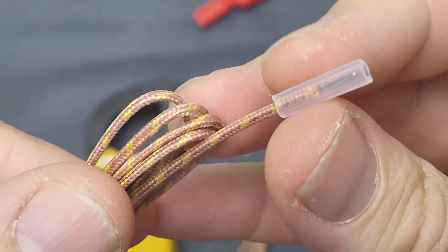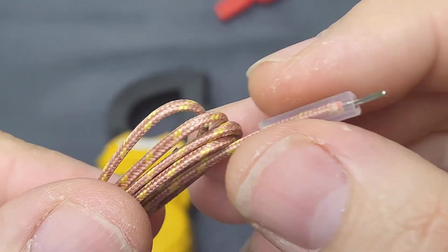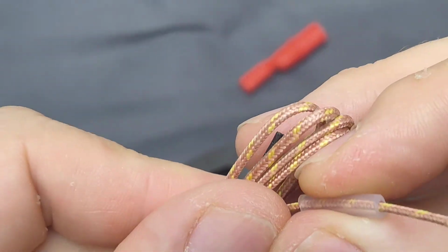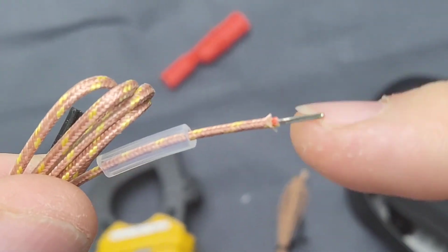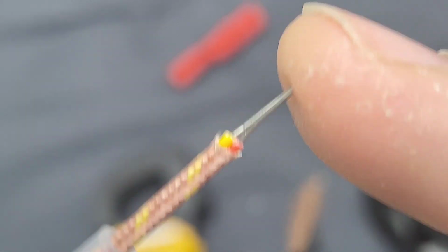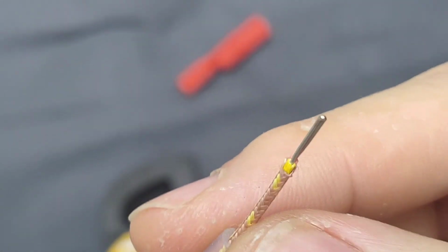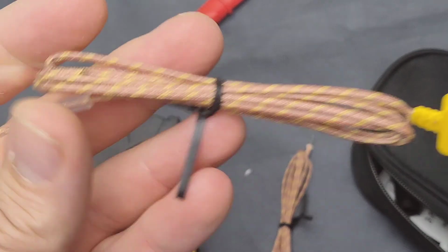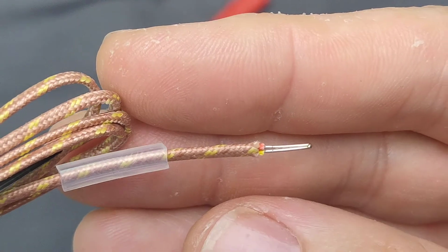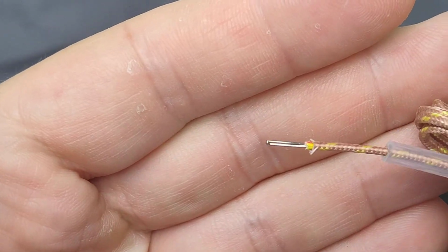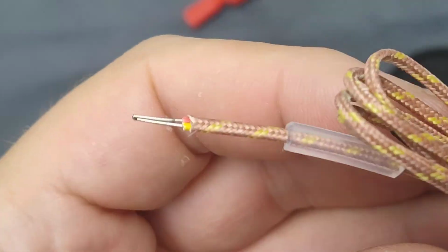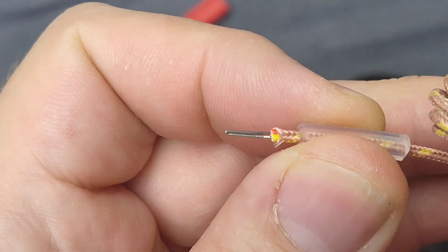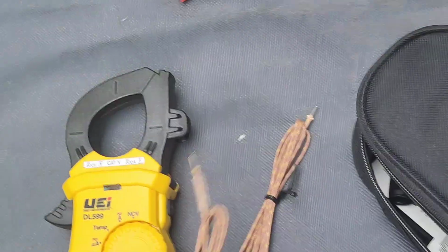Usually position that and put a little tape on it. I prefer to use a little bit of shrink tape around that, and that would measure temperature perfectly. So just by this you can use this as a differential temperature meter. Definitely you can do a lot of diagnostic stuff on an HVAC system, basically measuring differential temperature.